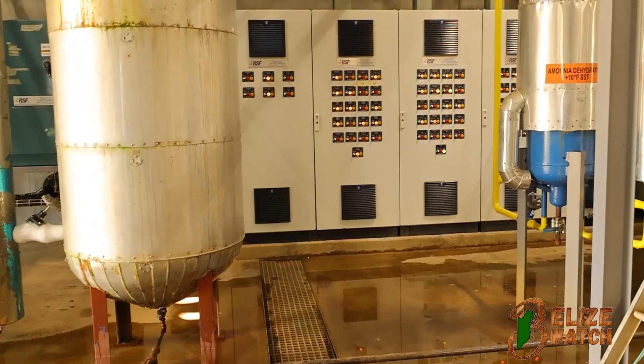The compressor takes the saturated gas and liquid that comes from the refrigeration rooms and turns it into high pressure gas. That high pressure gas goes to the condenser, which cools it, since it's also high temperature when it leaves the compressor. It cools it and turns it back into liquid.